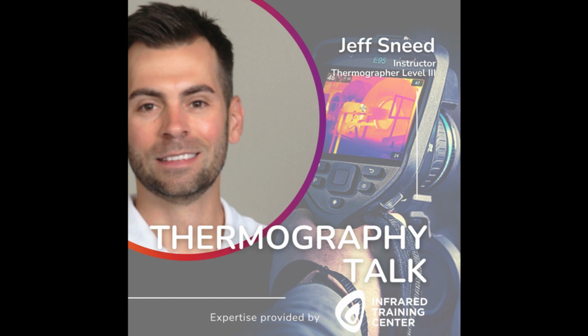One of the most common misconceptions in the industry is that arc flash clothing is stiff, not very flexible, and kind of itchy. So a lot of people put a lot of fabric softener in and wash them many times, but this is bad. The fabric softener can potentially be hazardous and could catch on fire. It also reduces the arc value of the fabric by making the clothes looser and stretching the fibers further apart, which actually reduces the arc flash rating.